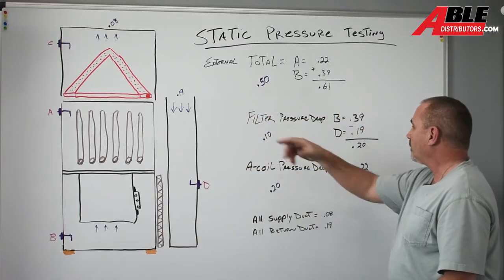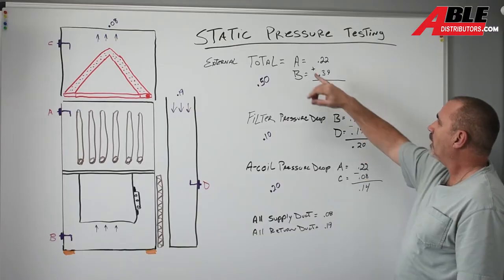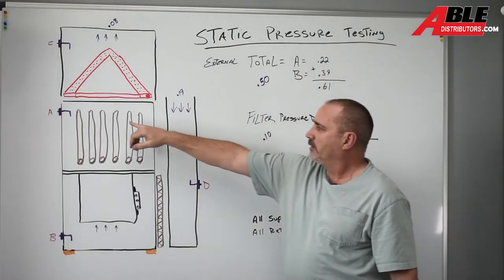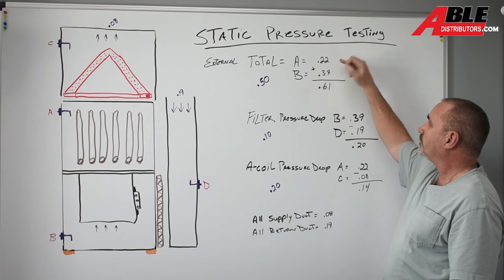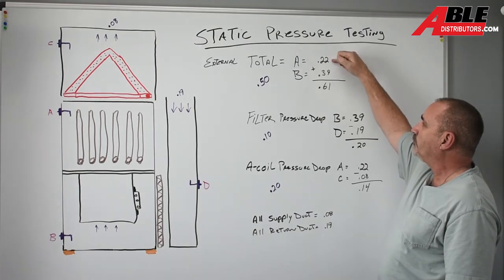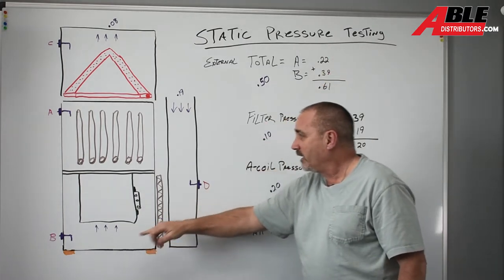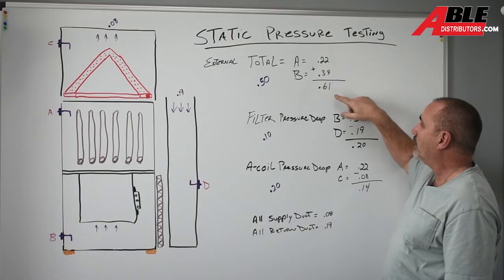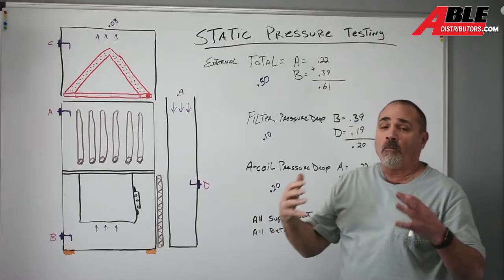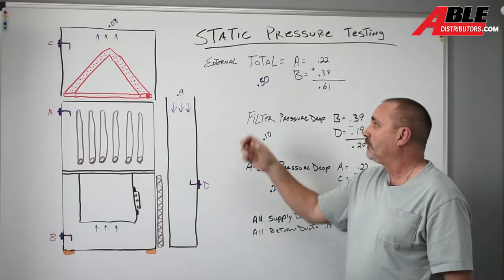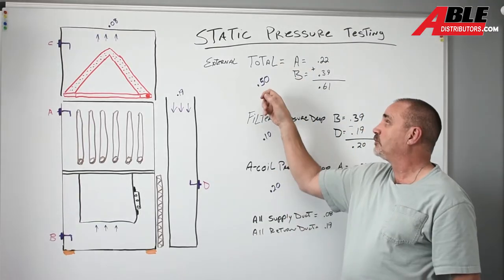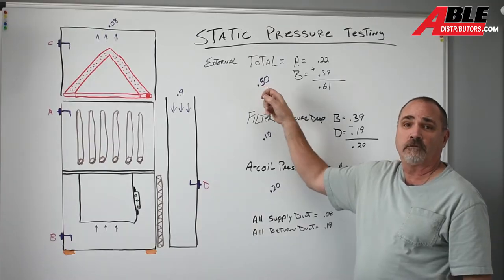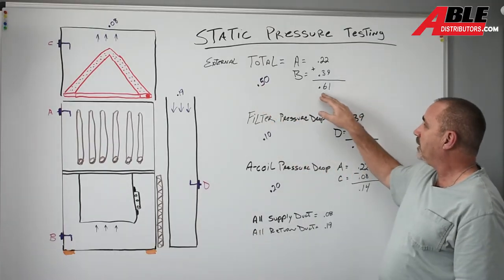So on this furnace, this was actually my sister's furnace, I had A, the pressure inside the furnace up at the supply side was a 0.22 and a negative 0.39 down below. We're going to add those up. It's 0.61. Almost every single furnace manufacturer out there wants a total external static pressure not to exceed 0.50. So obviously we exceeded it.